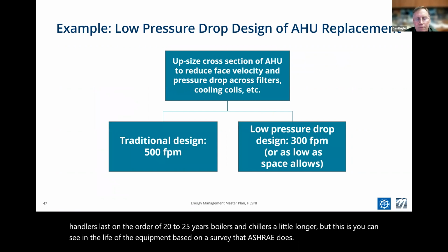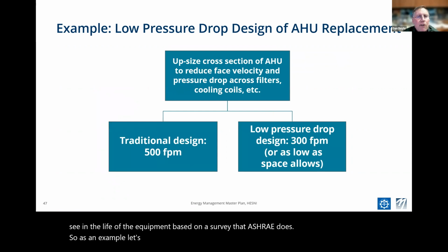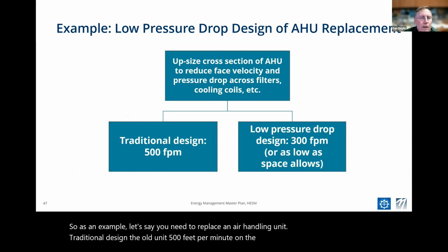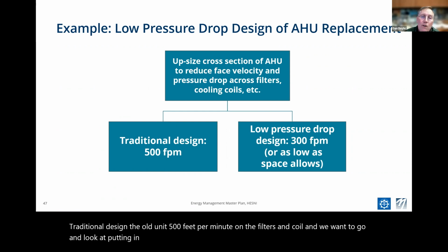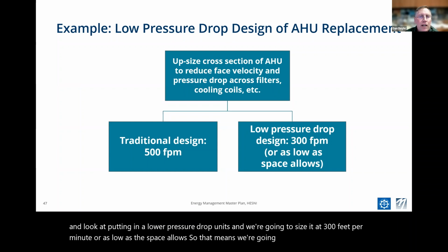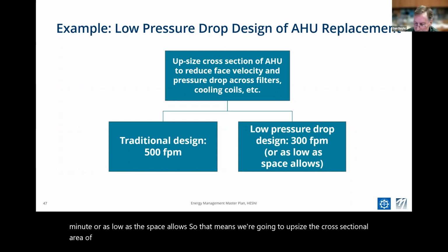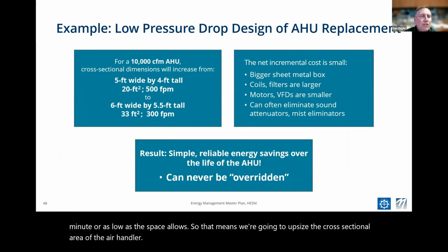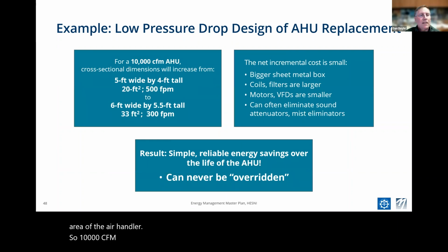So as an example, let's say you need to replace an air handling unit. Traditional design, the old unit, 500 feet per minute on the filters and coil. And we want to look at putting in a lower pressure drop unit. We're going to size it at 300 feet per minute, or as low as the space allows. So that means we're going to upsize the cross-sectional area of the air handler. So a 10,000 CFM unit: the existing unit is 5 feet wide, 4 feet tall.